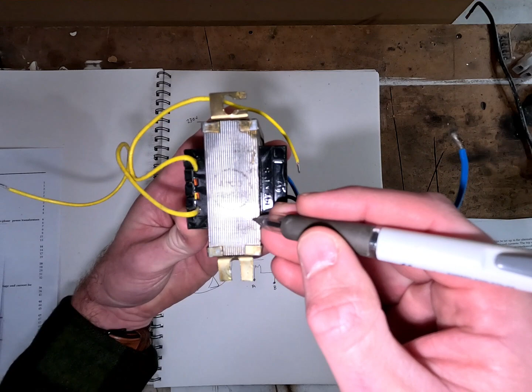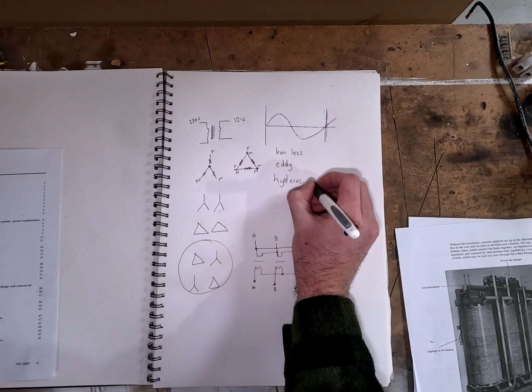Now, there are two types of iron losses. I'll write them down for you shortly. Both of them are a direct effect from magnetism from the electromagnetic fields. One of the ways they reduce the magnetism on the iron core is by laminating it with small sheets of iron which has varnish in between. You've got the eddy and the hysteresis. So if you want to know some more about that, search them up and have a look.